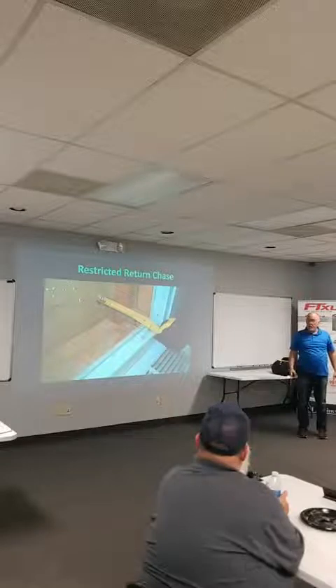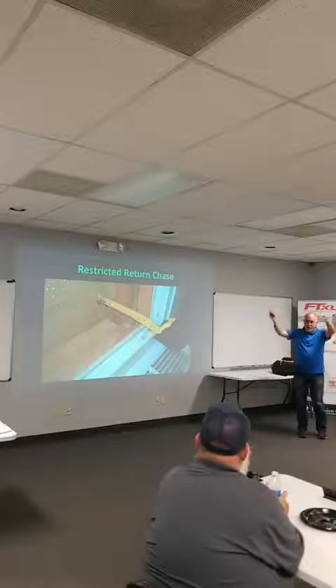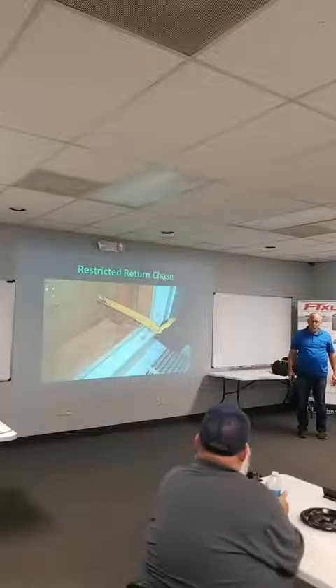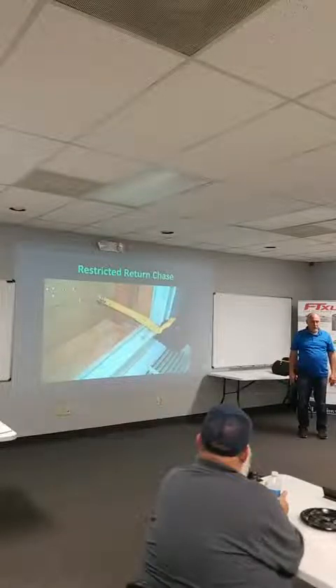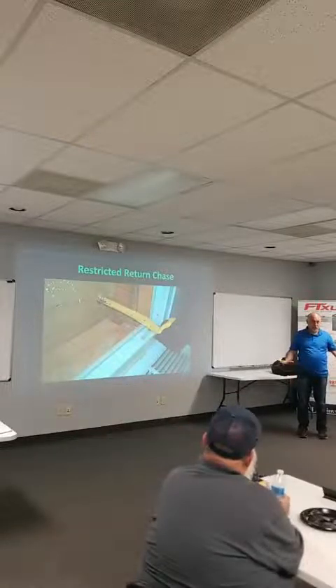So I walk in on the job, the guy's got a big drop on the furnace, and looking at everything, I'm like, wow, it's a nice looking duct system. So I put a static pressure probe in there, and it's drawing like 7/10 of an inch of static on the return. I'm thinking, wow, the filter must be plugged solid. I pull the filter out, it's still running 7/10 of an inch of static. I lost like 0.05 inches on my filter. The filter's not even dirty at all, right?